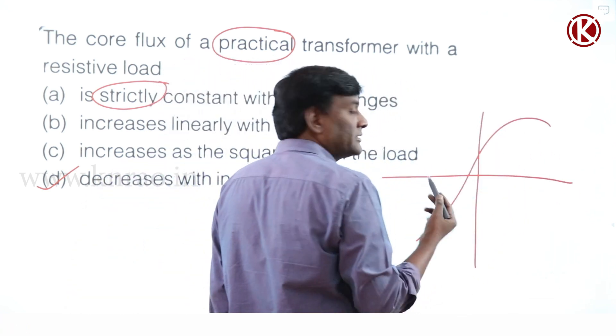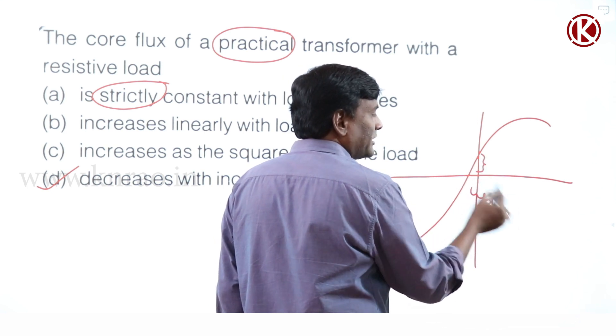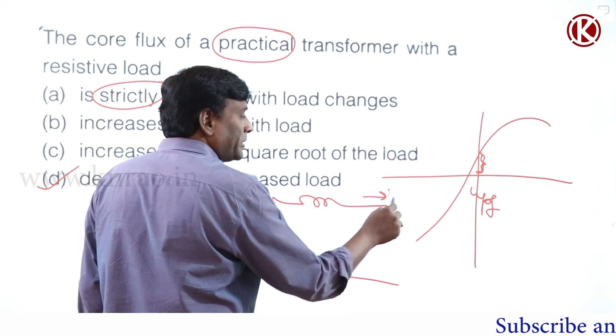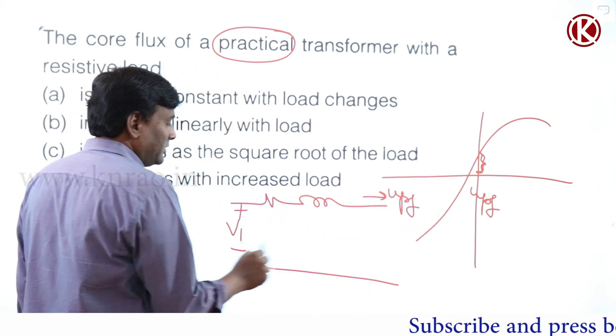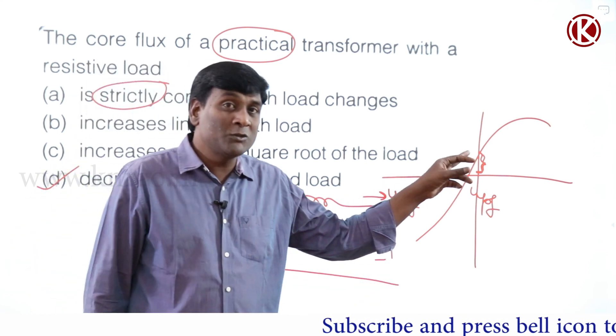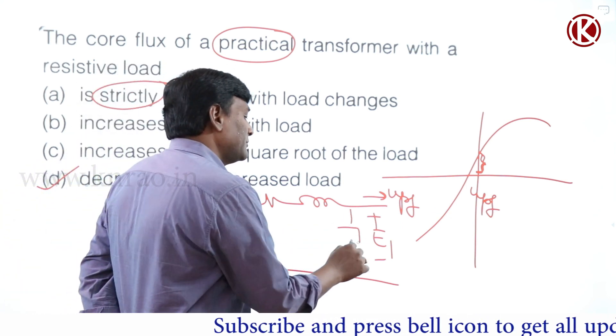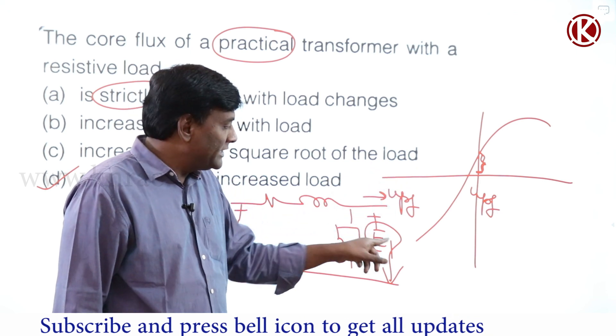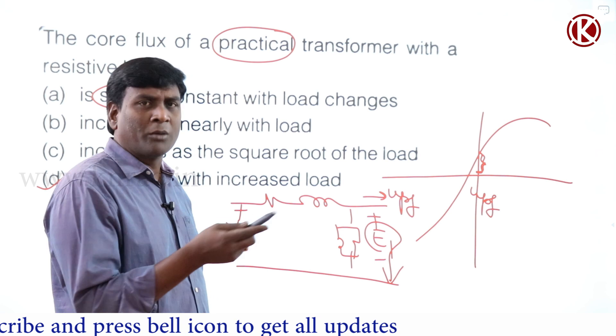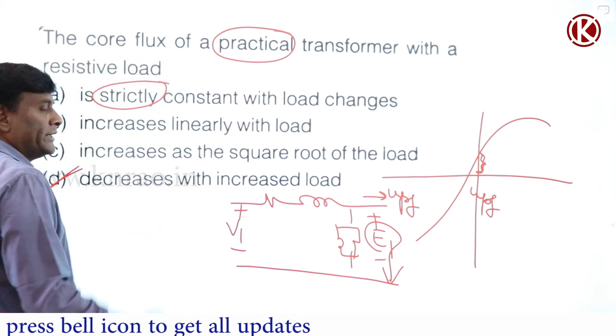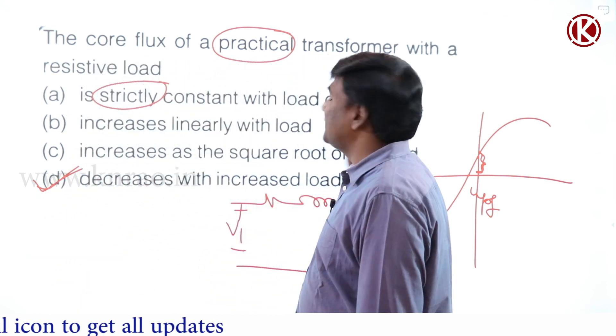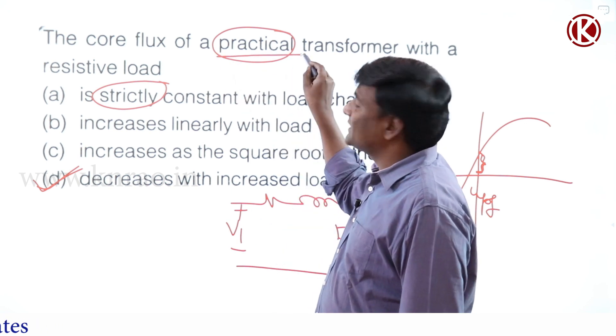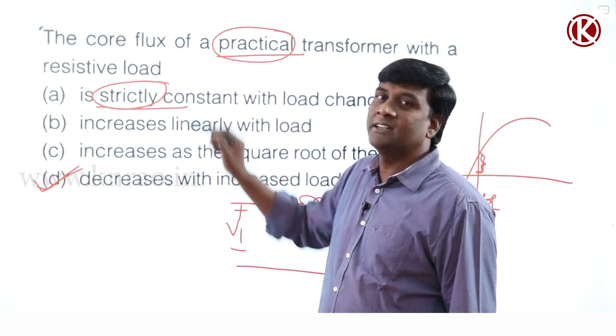We have seen the voltage regulation characteristic. At unity power factor, voltage regulation is positive. If it is operating at unity power factor with V1 and E1, and voltage regulation is positive, then compared to V1, E1 value will be less. As load current magnitude increases, E1 keeps reducing; as E1 reduces, E1 by F reduces and operating flux reduces. So 'decreases with increased load' is correct. We should not say it is strictly constant with load changes — those variations are normally neglected in transformer analysis, but the core flux is not strictly constant.